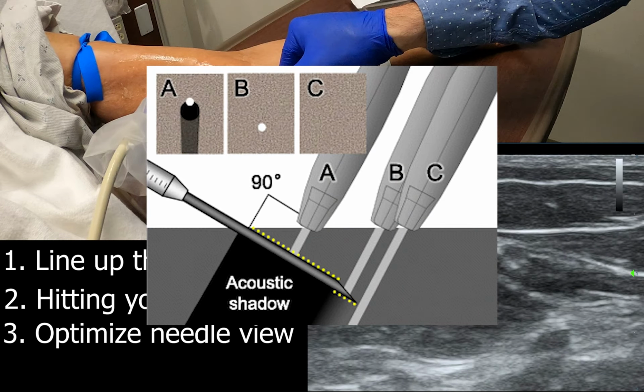So this is a graphic that's representing exactly what we just described. So here in transducer position A, you see that there's a good perpendicular angle between the transducer beam and the needle itself, giving you maximum brightness. So that's basically what I'm seeing there at the skin. Now what I'm going to do is I'm going to lock in that angle like we described, and I'm just going to slide the probe up the arm until I see an image that looks like B and then C. So what that's going to represent, as you can see, the beam just slides right off the tip of the needle, so I know exactly where the tip of my needle is in the soft tissue.